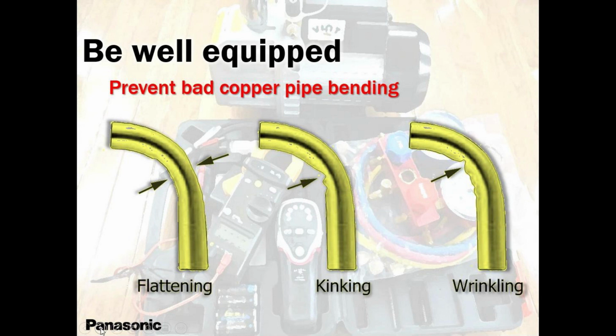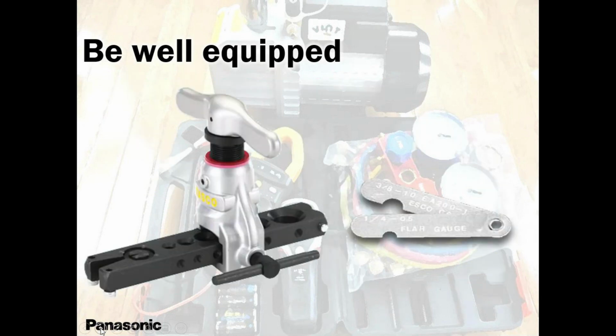Okay, not flattening the curve, guys. It's causing kinks here. Okay, please avoid these kinks. What can happen is it can cause the compressor to jerk. We went to a job site a while back. The compressor was stalling every time the pressure went up, and we found out that there was a kink. There was a kink just where the pipe exited the house coming down.